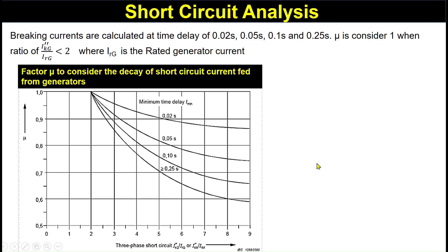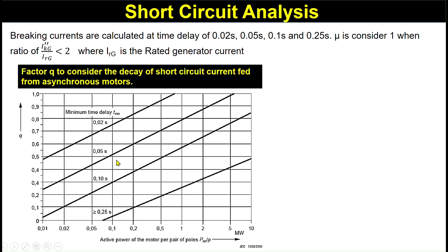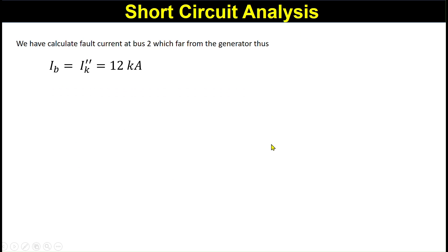You can also calculate the value of μ from this equation or from the curves, which show the ratio of ik''_g to ir_g against time delay. Similarly, the value of q can be read from curves showing the active power of the motor per pair of poles (P_M / p) against q at various time delays. Since we calculated the fault current at bus 2, which is far from the generator, ib equals ik''. You can verify this when performing the network analysis of this example.